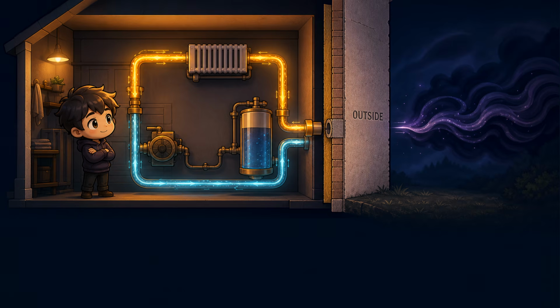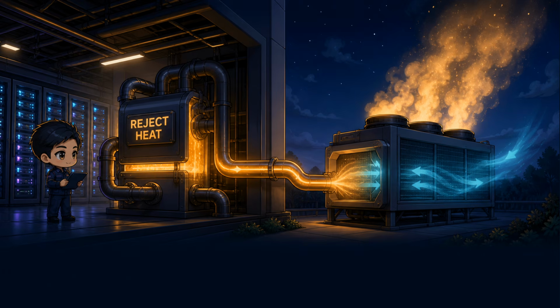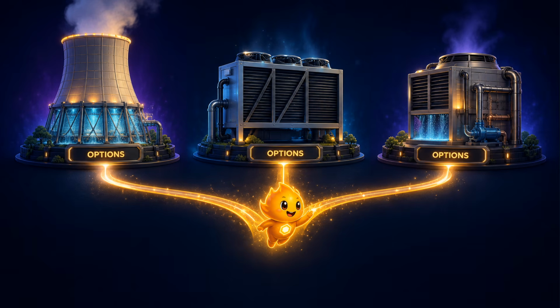But liquid cooling inside the building does not by itself answer what happens to the heat outside. The facility still needs a final heat rejection system. That system can use evaporation, dry air, or a hybrid of both.